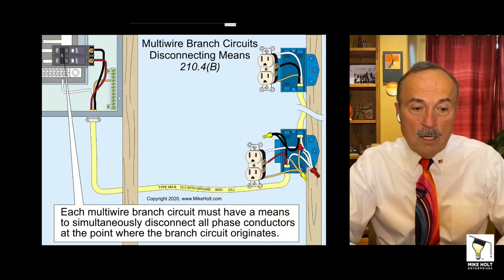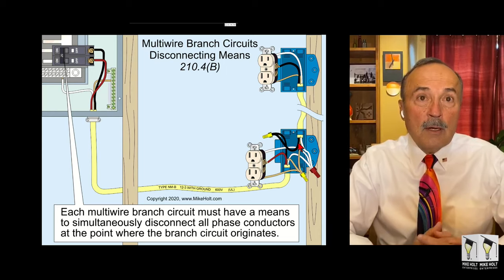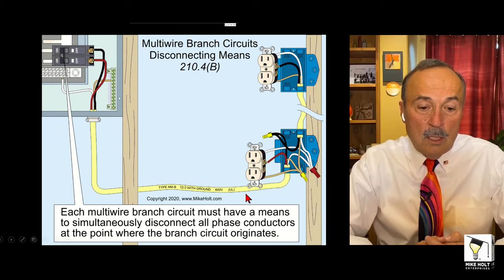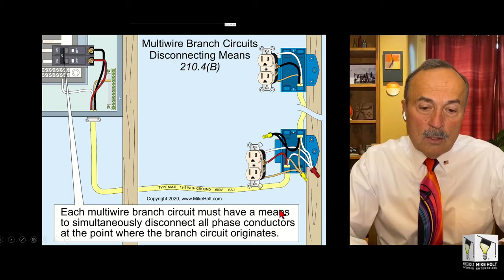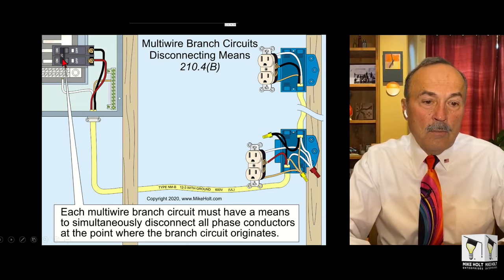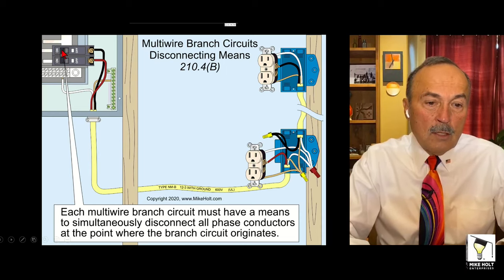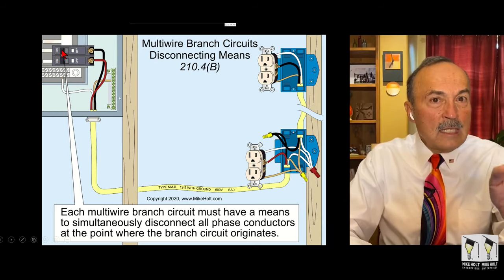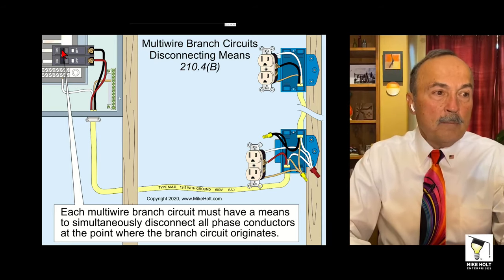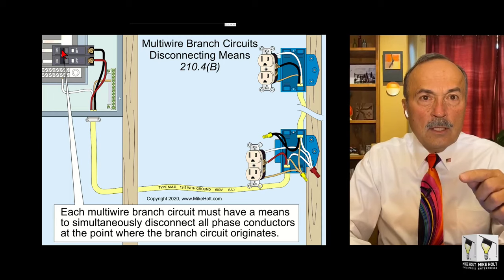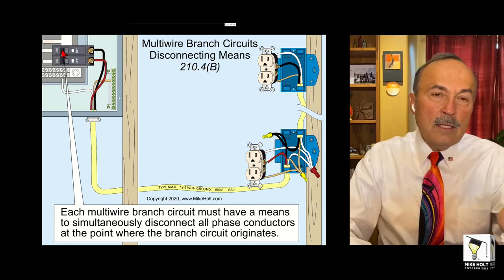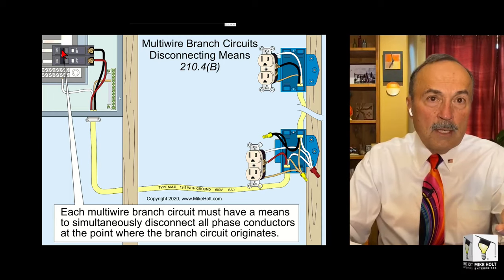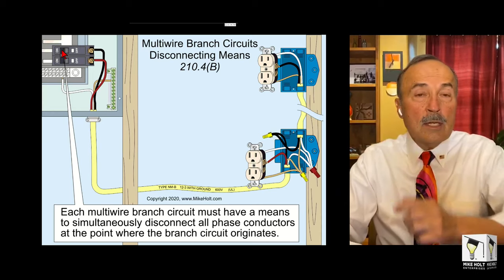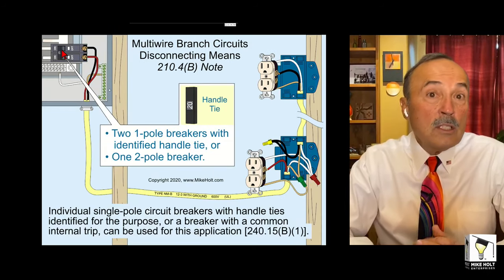That's the way it works. All right, no more questions. So back over here, finishing up AFCIs and multi-wire branch circuits, the code requires each multi-wire branch circuit must have a means of simultaneously disconnecting all phase conductors at the point where the branch circuit originates. So you can put like a two-pole breaker. So you have to have a way to simultaneously disconnect. That doesn't mean that if one phase trips, the other phase of the circuit breaker has to open. It just means that you have to mechanically get there and turn that sucker off. And what does the code permit?